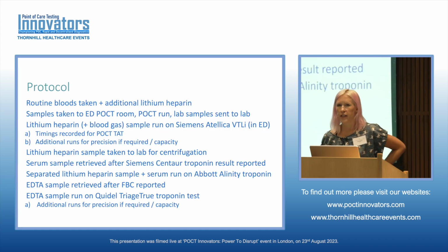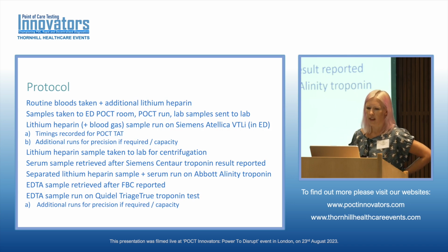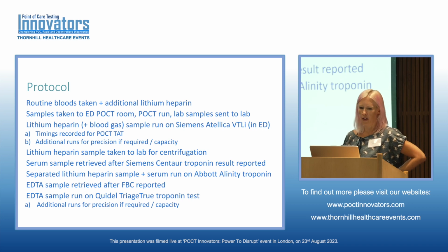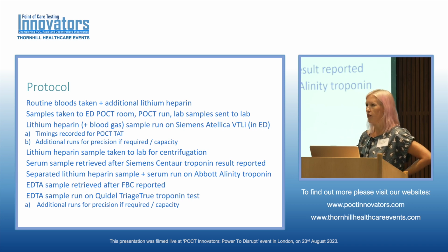So the protocol was that Katie, Bethan and I stood in ED, or one of us stood in ED, and the routine bloods were taken by the ED staff with an additional lithium heparin, for which we only needed verbal consent from the patient. They were taken to the ED point of care room and run for their usual point of care, and the lab samples were sent to the lab. We got the lithium heparin, which wasn't required usually for the patient, and we also took the blood gas sample, and we stood in the ED room and ran those on the Siemens Atellica VTLi.